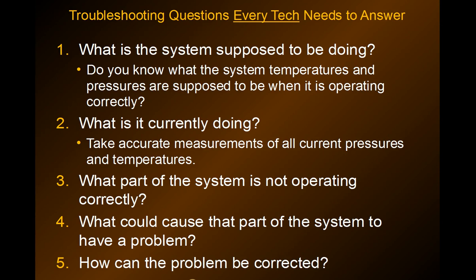The thing you need to remember with commercial refrigeration is there's a lot of different pressures and temperatures and box temperatures, unlike residential air conditioning. So you really need to know what the system is supposed to be doing. And it's very difficult when you do commercial refrigeration to know what the system's temperatures and pressures are supposed to be when it's operating correctly, because the installation and operation guides and specs are usually long gone. The systems have been hacked and repaired and re-put together time and time again by the time you get there. So it's very difficult to do.